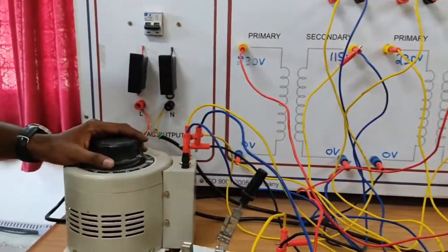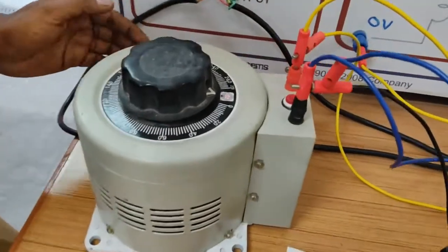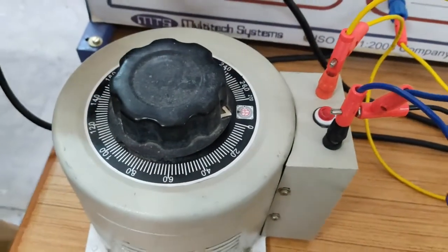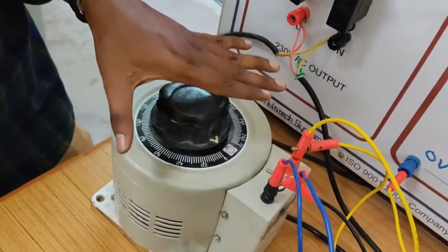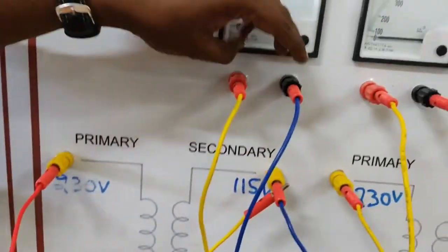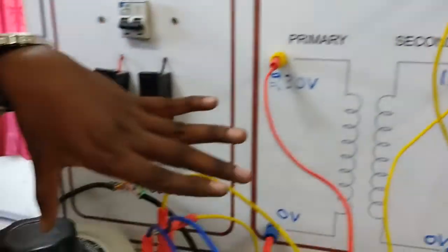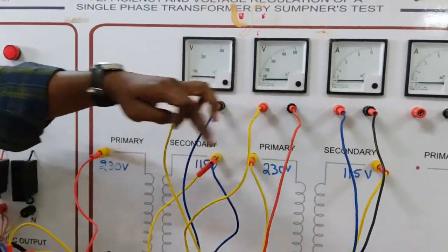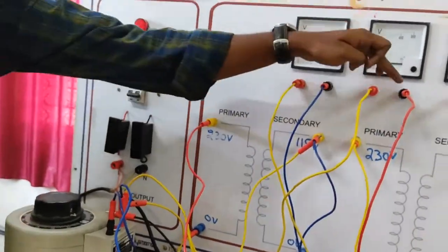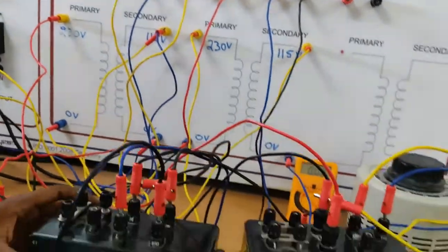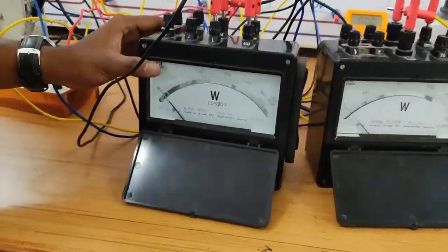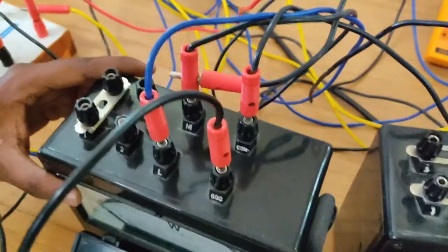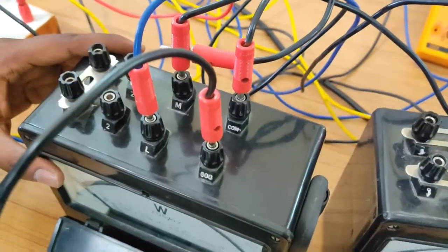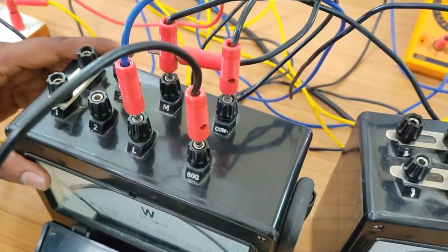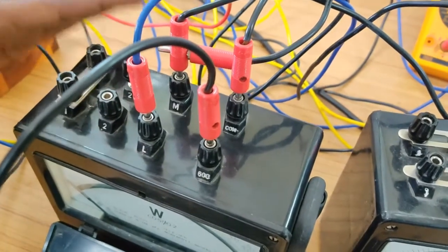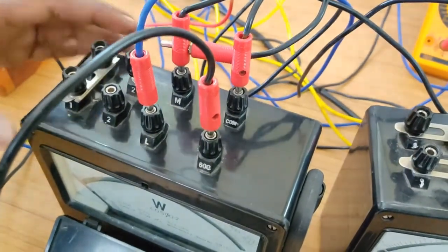So first, this is the first auto transformer, the first variac, right? These terminals I have given to the supply, plus to plus, minus to minus. Next, across this auto transformer, I am connecting one voltmeter, plus to plus, minus to minus. Next, the ammeter positive should be connected to the auto transformer positive, and the ammeter negative should be connected to your wattmeter LPF. So the Sumpner test is nothing but a combination of OC and SC tests, but instead of doing the OC and SC tests separately, we are performing the Sumpner test. So the ammeter negative should be connected to the LPF wattmeter.